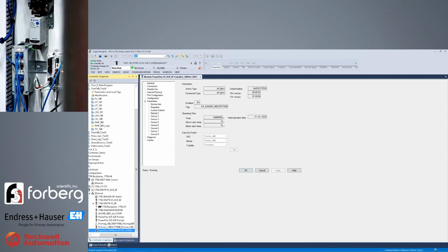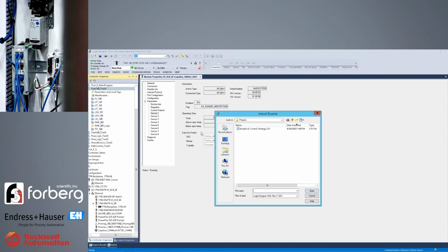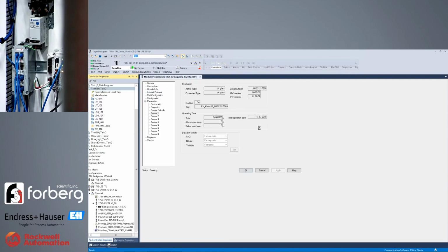At this point, we've added our device into our Ethernet I/O tree. So our next step is to add some programming, but instead of creating custom programming, I'm going to use one of the provided instruction types available for the Endress+Hauser instruments in the PlantPAx library of process objects, by importing a pre-built process strategy. So I come up here, import a routine, and grab this particular routine.